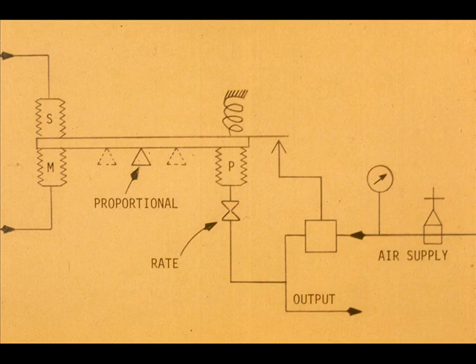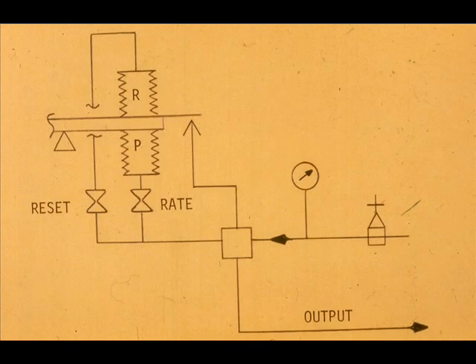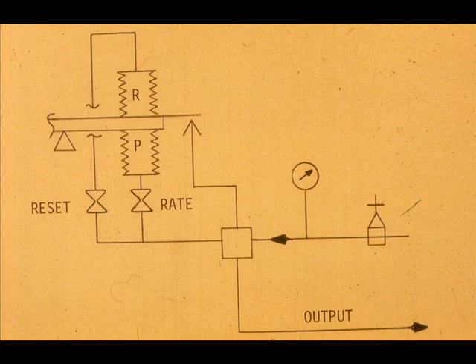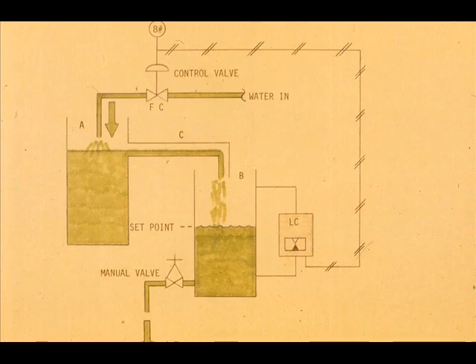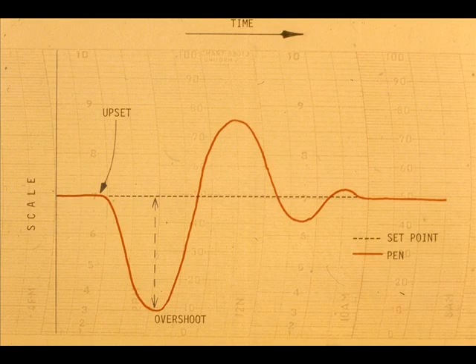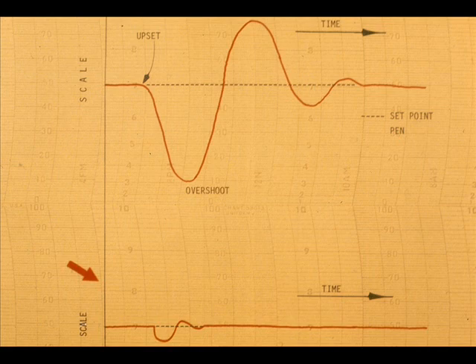A controller may have proportional plus rate, or it may have proportional plus rate and reset. Whereas the measurement or response curve for our hypothetical process may look this way without rate action, it can look this way with the addition of rate. By advancing the control valve action, the overshoot is reduced.